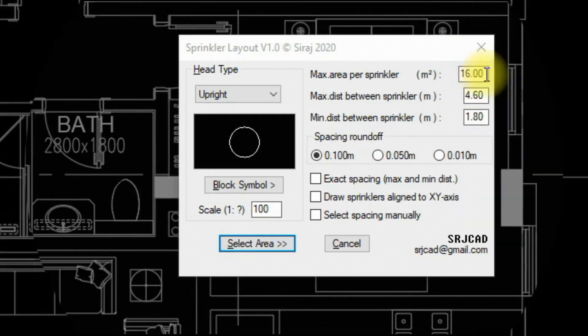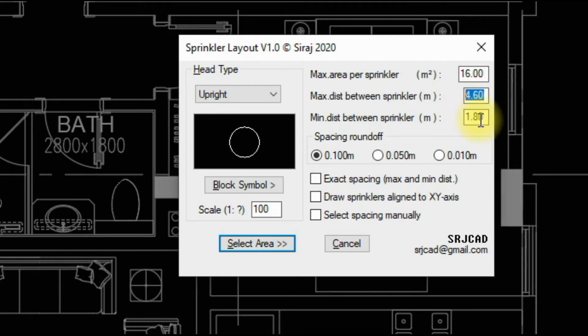This edit box is for maximum area per sprinkler, this box is for maximum distance between sprinklers, and this box is for minimum distance between sprinklers. Sprinkler spacing roundoff can be assigned using these radio buttons. Scale of the block can be changed using this edit box. Normally, keep the scale of the block the same as the scale of the drawing being made.